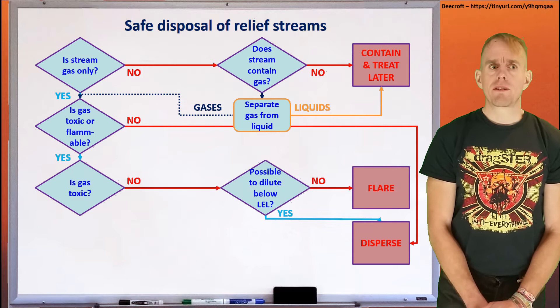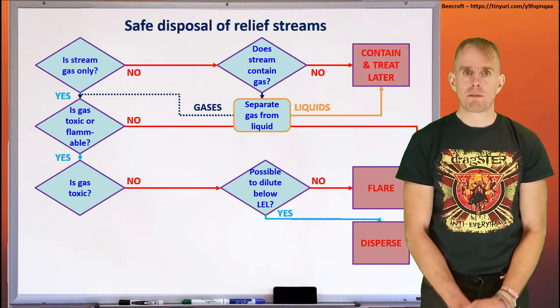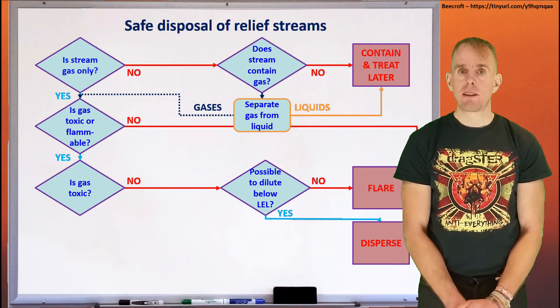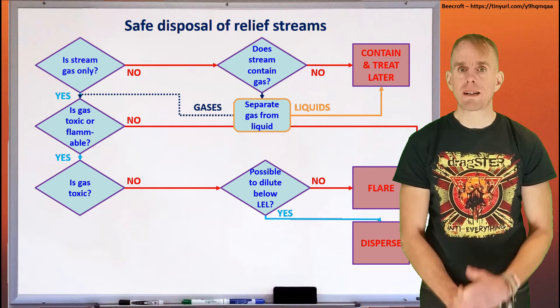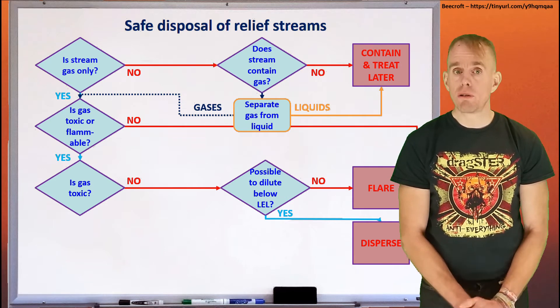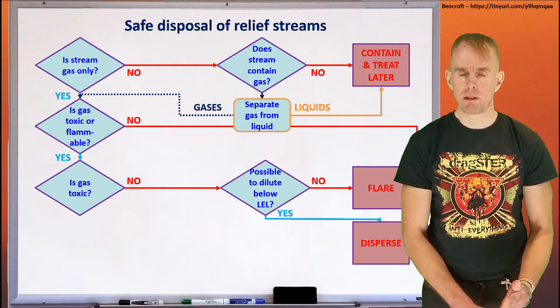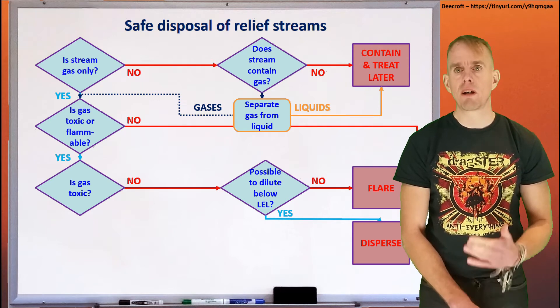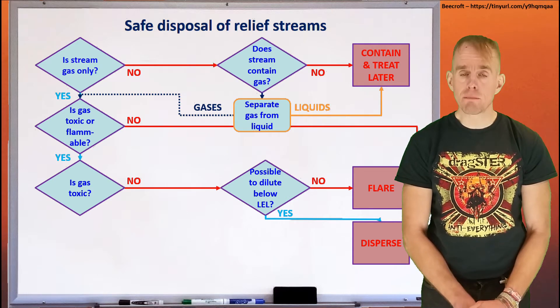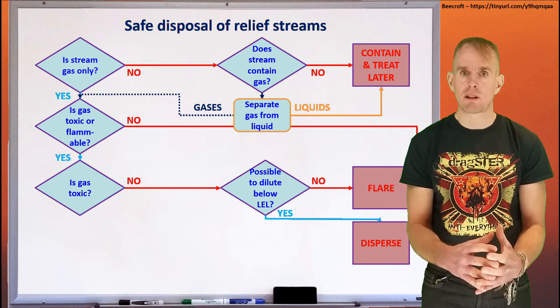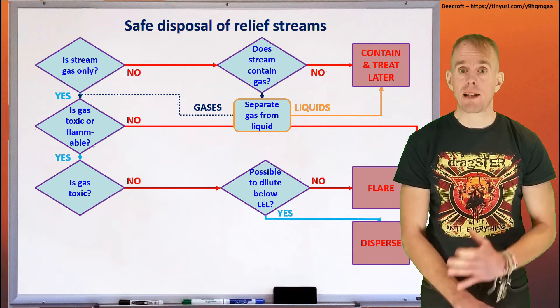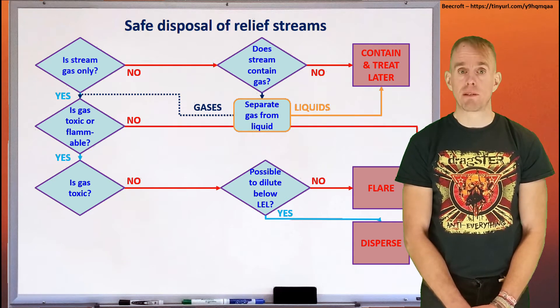On the assumption that the gas is either toxic or flammable, the next question to ask is: is the gas toxic? If not, and you're dealing just with a flammable gas, then you have to consider whether it's possible to quickly dilute that flammable gas below the lower explosive limit. If so, what you can do is disperse it through a relief valve. This might sound somewhat surprising, but you'll find a lot of relief valves on refinery operations vent straight to atmosphere, but do so in such a way that lots of air is sucked into a turbulent plume, which ensures that the lower explosive limit is never reached and that whatever is relieved cannot be set fire to.